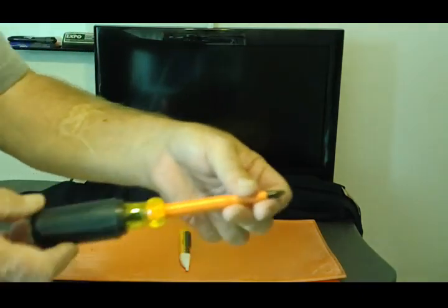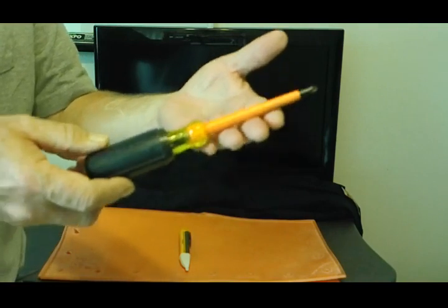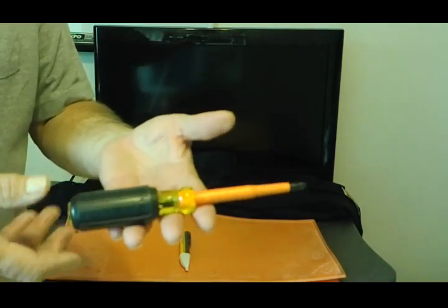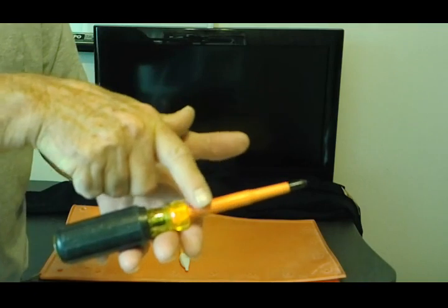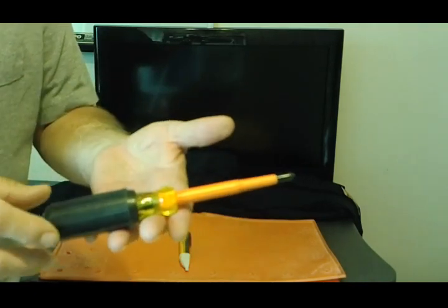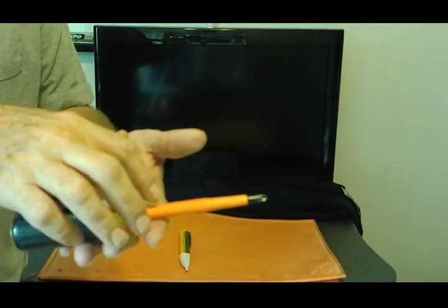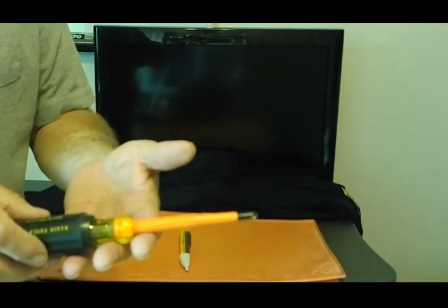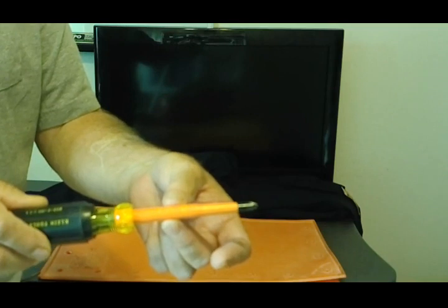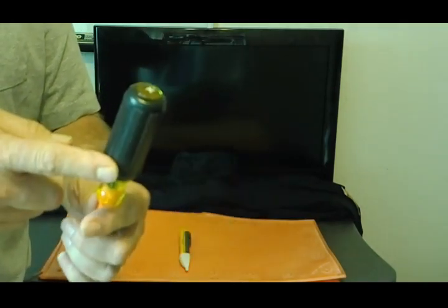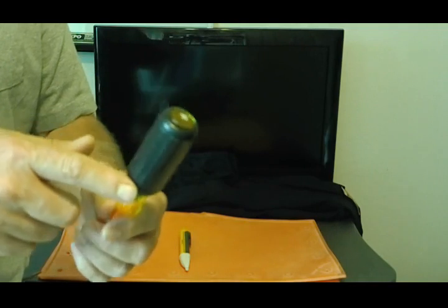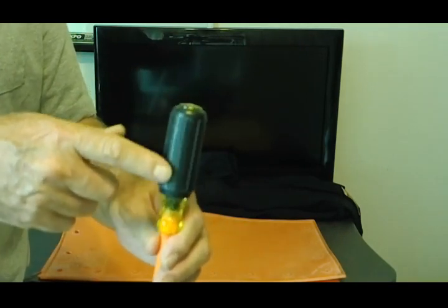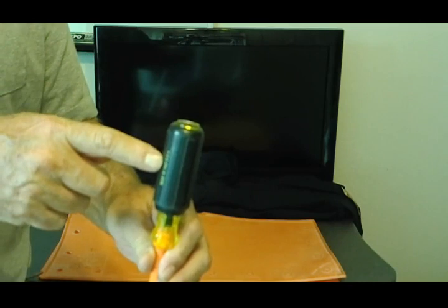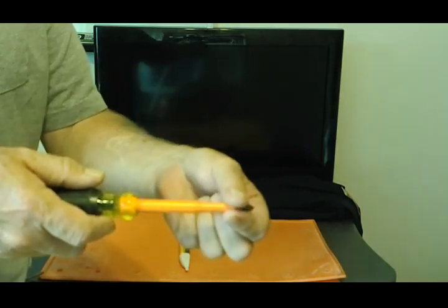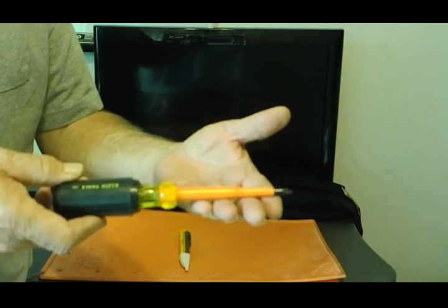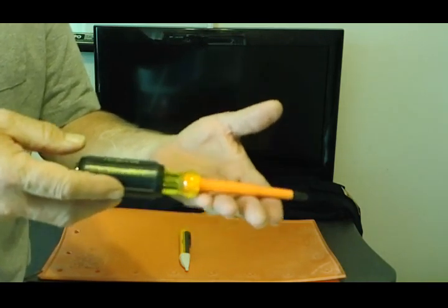Now we look at tools like this. Here we got an insulated tool. These are everywhere. Everybody's got them these days. This orange part is the insulation, usually rated to 600 or 1000 volts. It's very tough, very stiff, and hard to damage. This handle on this tool has no insulating capabilities whatsoever, so this is not an insulator. This is a comfort grip. The insulation's right here. So this tool, even though it's rated 1000 volts, is not rated for shock protection.